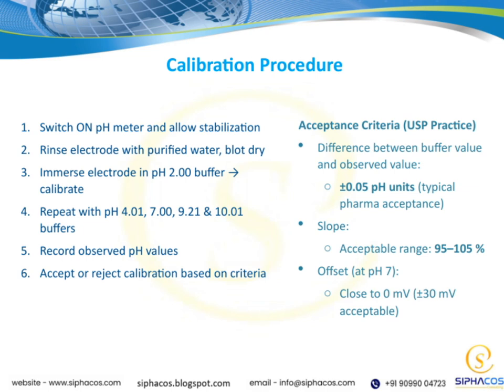First, when we talk about the difference between the buffer value and the observed value, a typical pharma acceptance is within plus or minus 0.05 pH units. This ensures our measurements are accurate and consistent. Next, the slope of our calibration curve should fall within an acceptable range of 95 to 105%. This range indicates that the electrode's response is reliable and linear across the pH span we're working with.